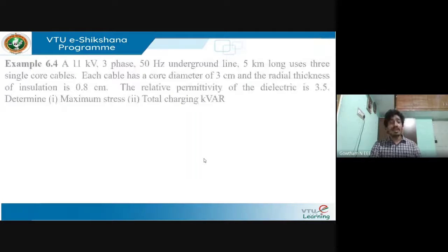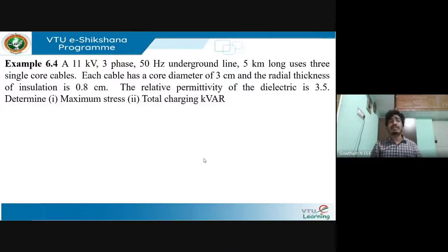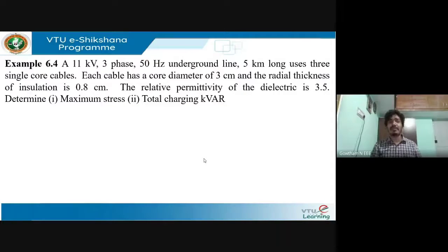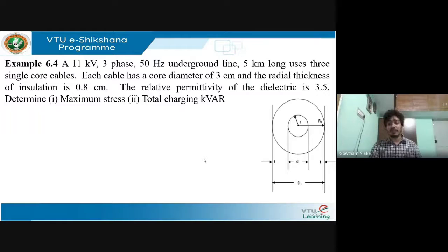The next problem: an 11 kV three-phase 50 Hz underground line, 5 km long, uses three single core cables. Each cable has a diameter of 3 cm and radial thickness of insulation of 0.8 cm. The permittivity of the dielectric is 3.5. We are to determine the stress and the total charging kVAr. A diagram is used where thickness t and diameter d are identified.